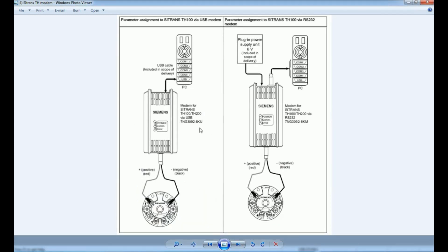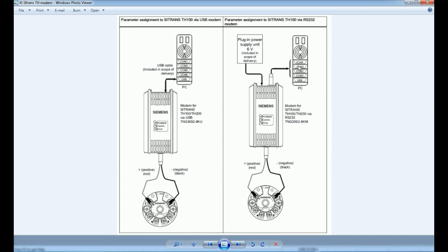For the HART modem connection, the positive and negative terminals are connected with the power supply and from there we get the USB cable that connects to the PC. Since we have connected a resistor, we connect the positive and negative terminals across this resistor to get the 1 to 5 volt peak voltage, which is used as the HART signal. If using an RS232 modem, we connect the positive and negative terminals to power supply and the RS232 port to the PC.